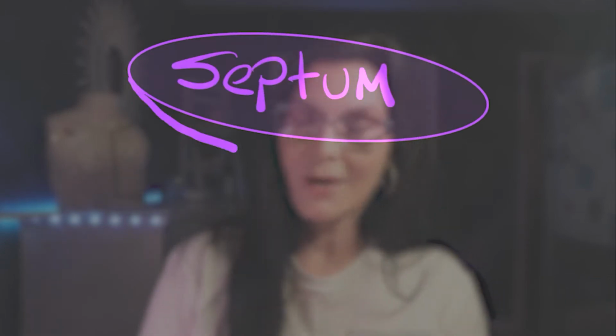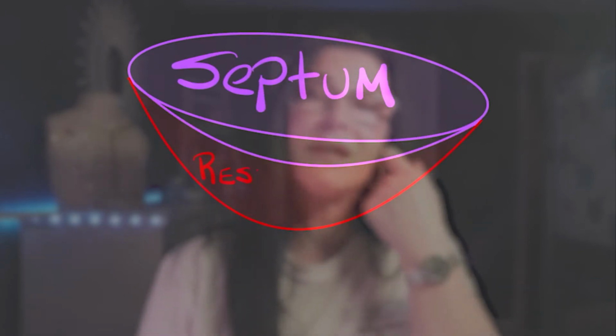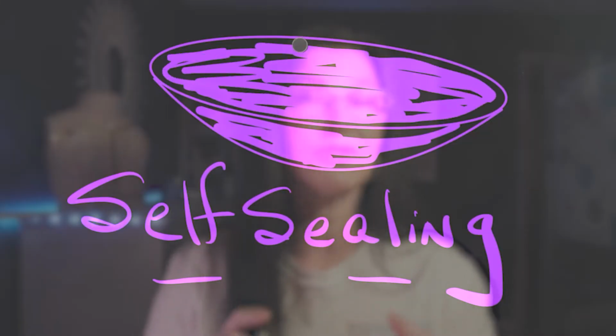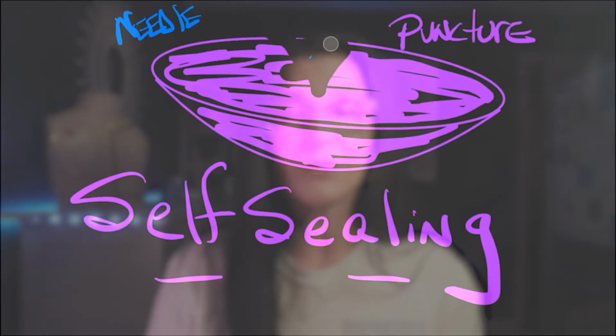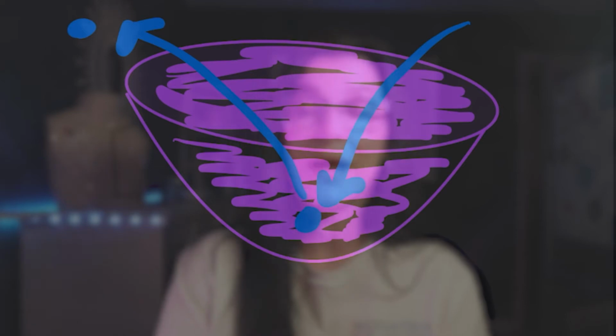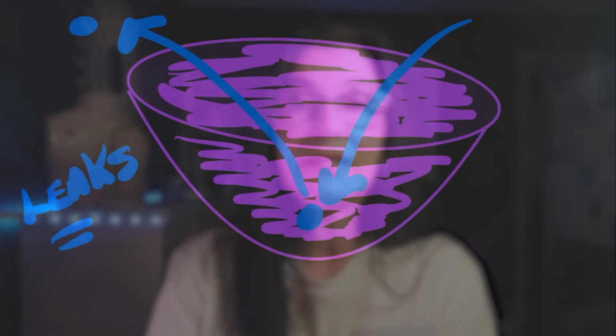So this body houses the septum and the reservoir. The septum is typically about the size of a dime, maybe a bit smaller, and it's made of a self-sealing silicone, meaning after each needle removal, the puncture area closes back up. And this is key because ports are intended for long-term use, months to years. So if each time we inserted a needle, it removed or cored a piece of silicone out with it, then this would eventually lead to leaking and render the port useless and even dangerous to continue infusing through. So that's why we only use certain needles, which I'll get to in a little bit.